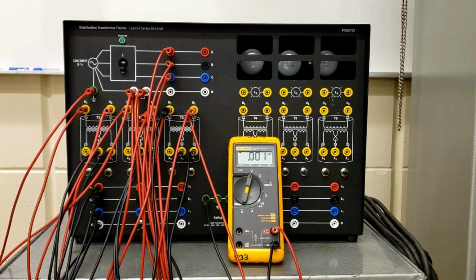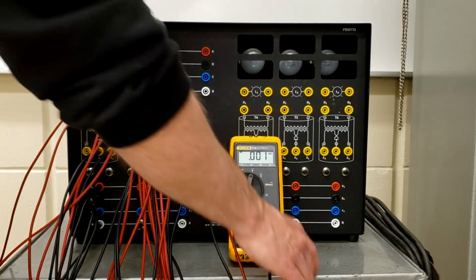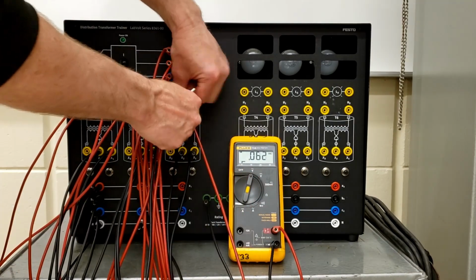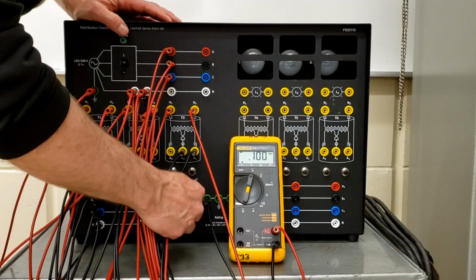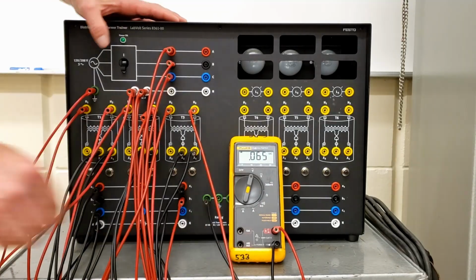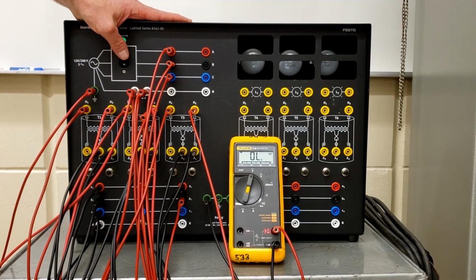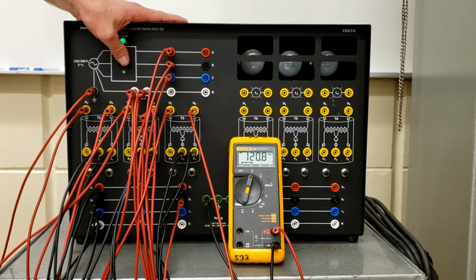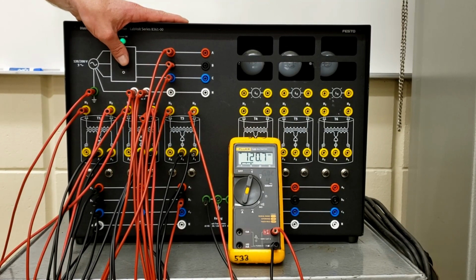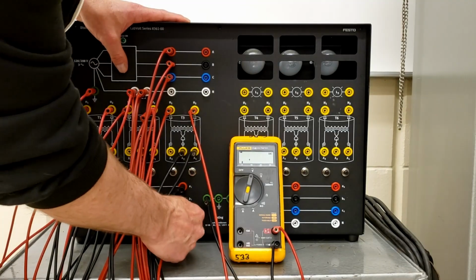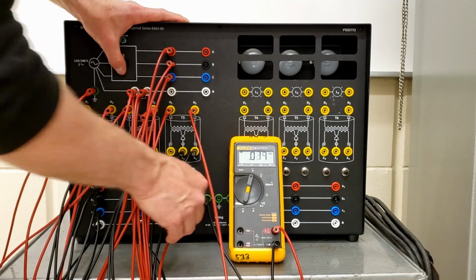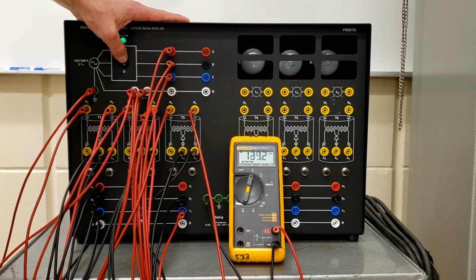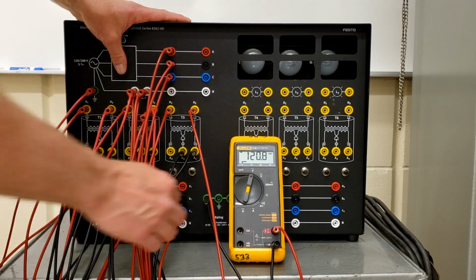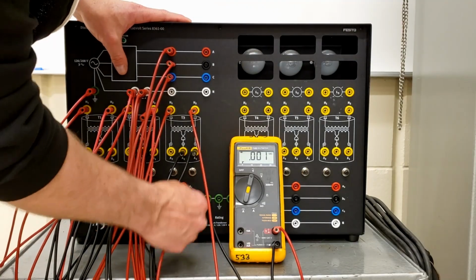They're asking for the voltage between the lines, so let's do that first, then we'll look at the phase voltage on the secondary. Between A1 and B1, let's see what we got. So we have 120 — that's our line voltage on the outside of the Y. Between B and C we should also have 120, and between C and A we should also have 120.